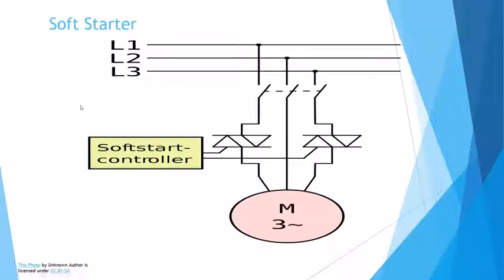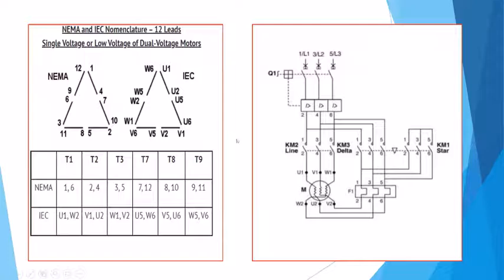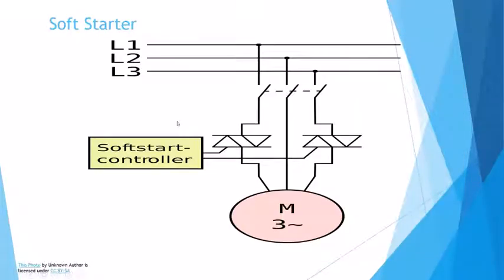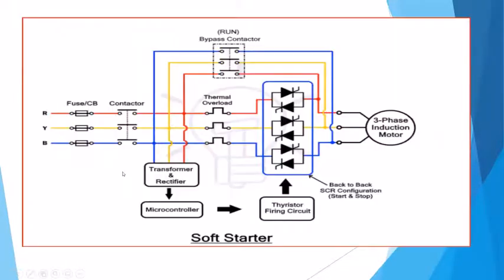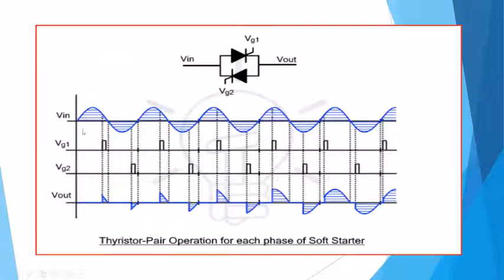From that point, then they developed the soft starter, and this is that patent that Nolan created. And these are basically thyristors here, and instead of having all the combinations of starters and contactors and time delay relays and all this stuff, they're basically able to trim the actual power. So when the motor came on here, they would turn these thyristors on and off, and you'll see more of a pulse train here. So here's the original voltage waveform. Then they started turning it on just a small amount.